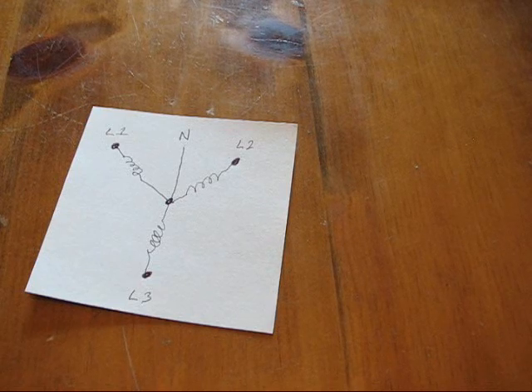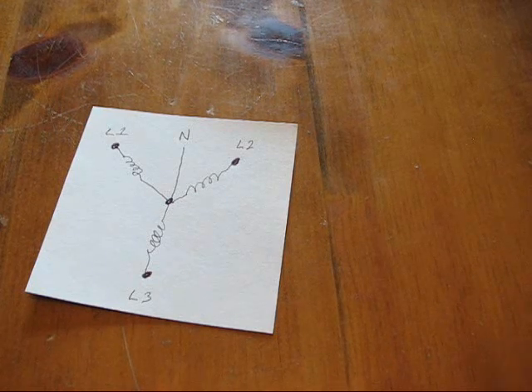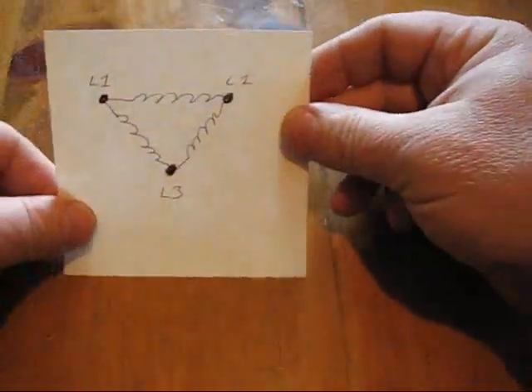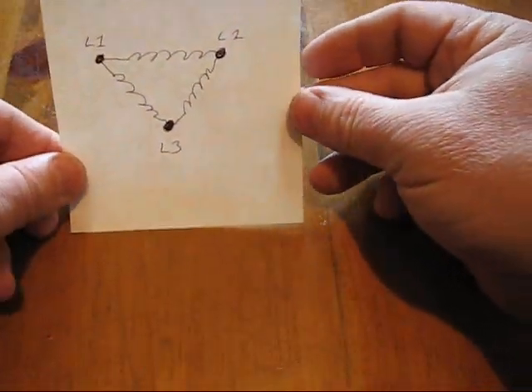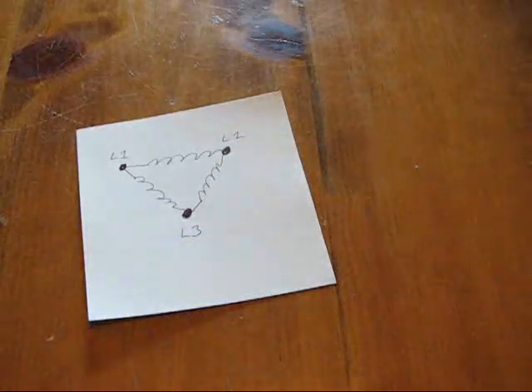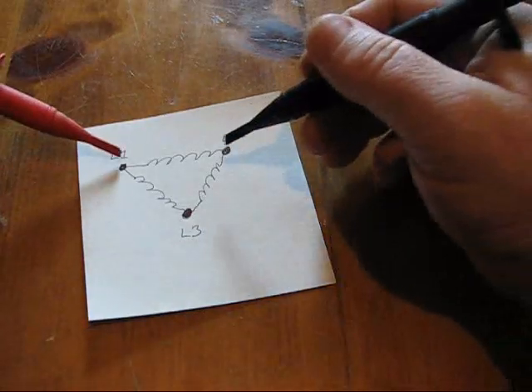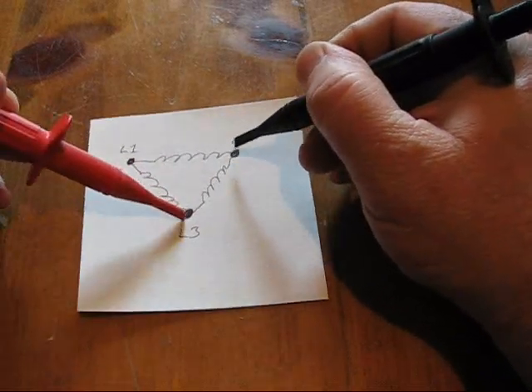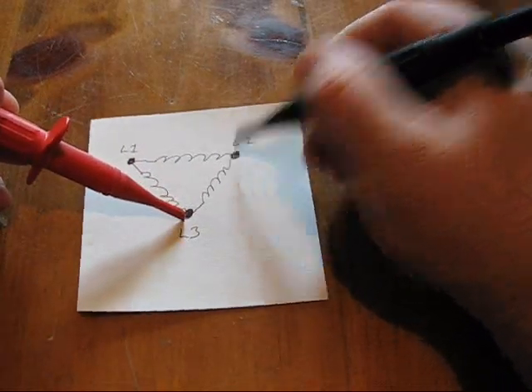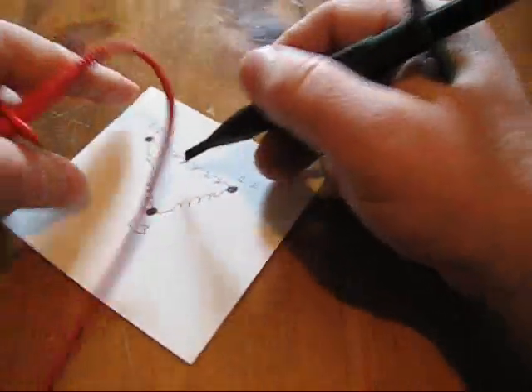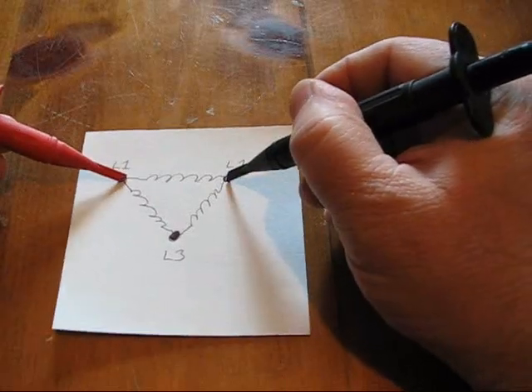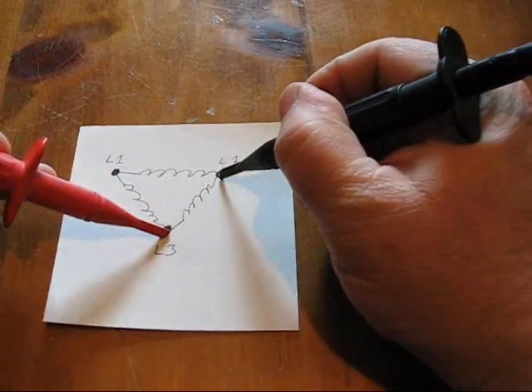Now another method of connection of a generator, a three phase generator, is called the delta connection. In that case, there's no neutral. All you have is across the hot legs. Across each of those, instead of it being a 110 volt coil, it's 220 volts. So 220 across any two connections.